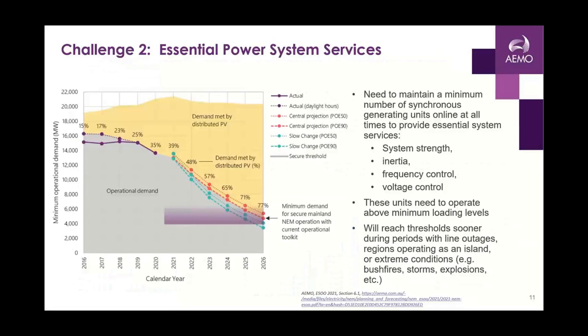So the next challenge, and I'm conscious about time, is looking at essential power system services. As I mentioned, our load is declining quite significantly, but at the same time, we also need to make sure that we have large generators that provide a lot of other services to us. So a big coal plant actually provides us a lot of system strength, inertia capability, as well as frequency control and voltage control.